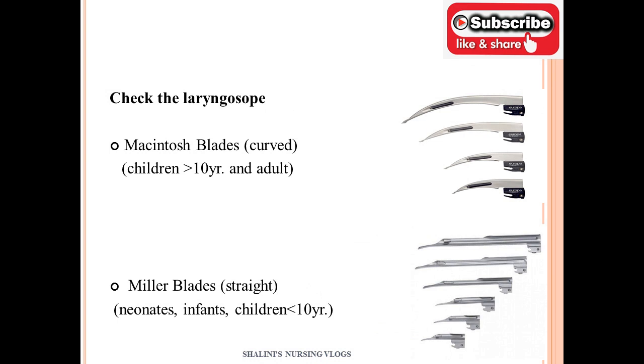Check the functionality of the laryngoscope: verify that the blade slides properly into the handle and that the lighting is functional. There are two main blade types: the Macintosh blade, a curved blade commonly used for adults, and the Miller blade, a straight blade used for the pediatric age group.